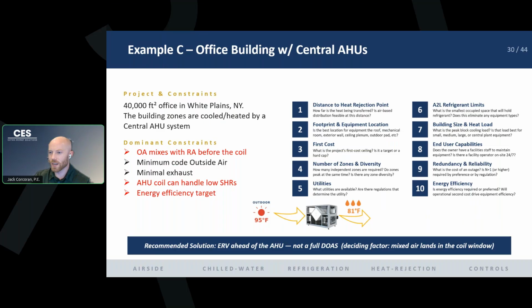which is right in line with what a regular central air handling system can handle, right? You can have a larger coil on your air handler if it's sitting in a mechanical room, so it can handle the latent loads that a VRF system can't. So we can get away with just using an ERV in this situation, tempering it only slightly, using that free cooling and free heating in order to allow the system to properly reach its set points, right? You don't need the DOAS system to totally dehumidify it because our air handling units can already do that last step of dehumidification we need.